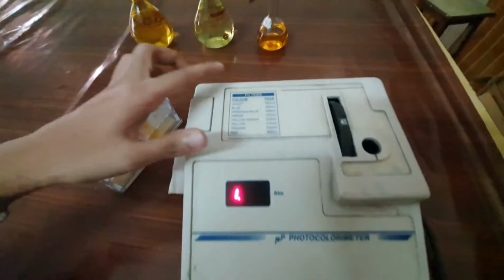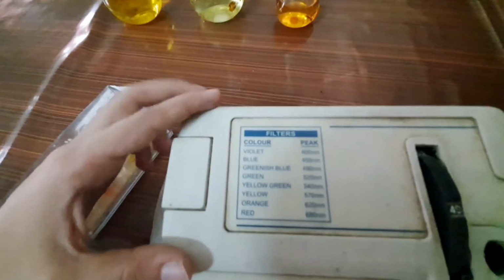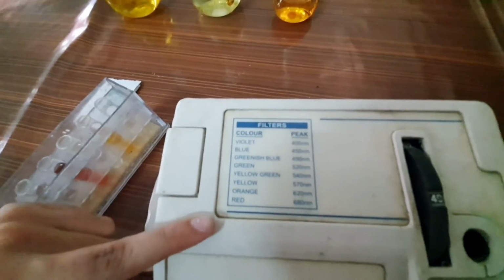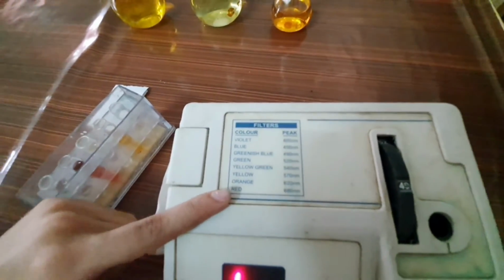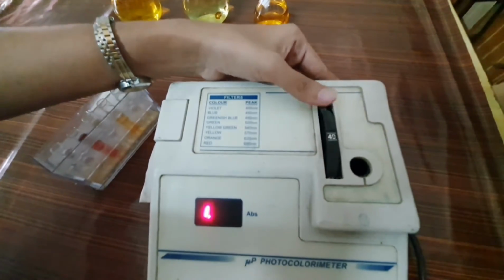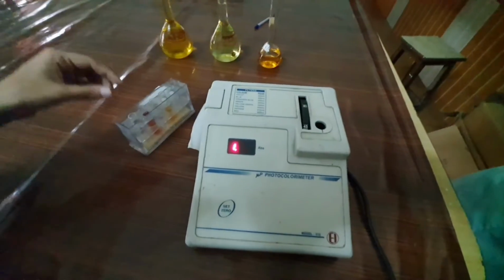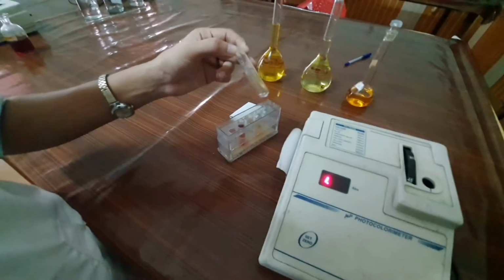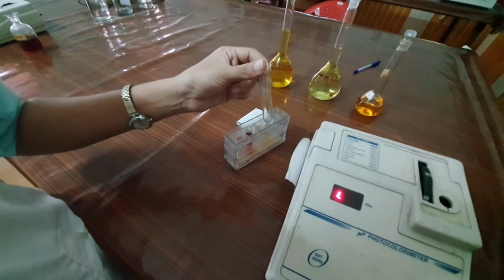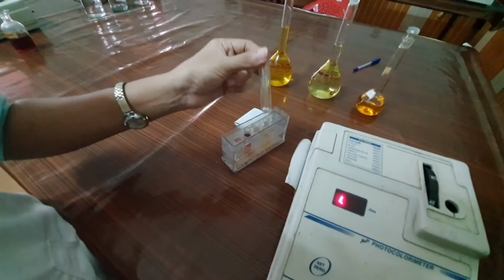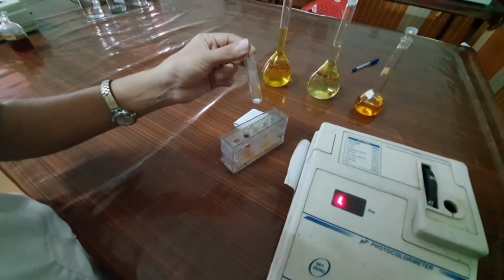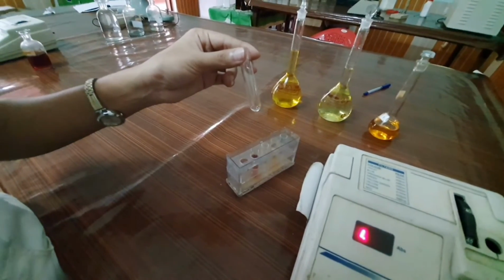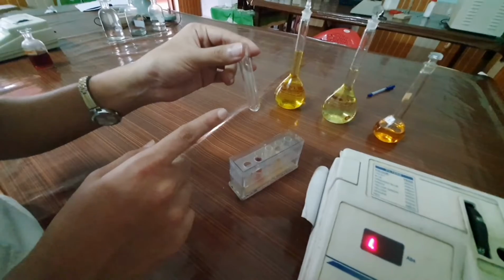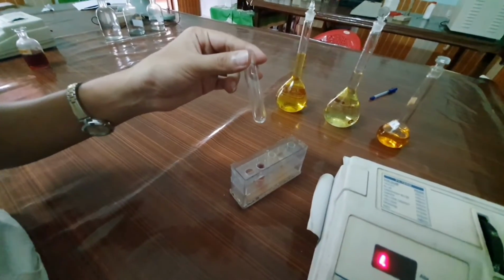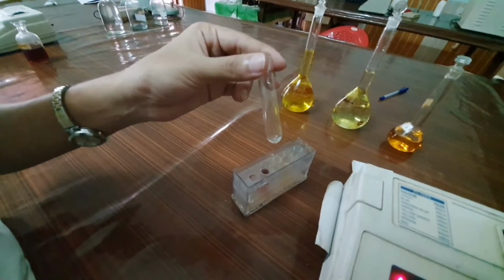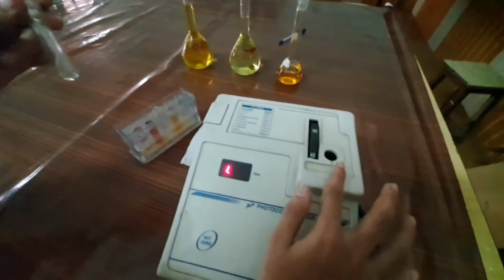Filter. It absorbs most of the light and permits only the light of the corresponding color. We can change the filter depending on our requirement. Cuvette. It is a glass material. Make sure there are no contaminations and no scratches. Hold it at the top. If held at the bottom, fingerprints will be impressed, which will affect the transmittance of the light. This is the cuvette holder.